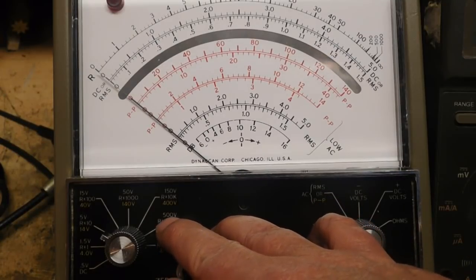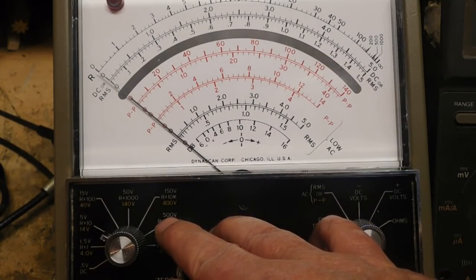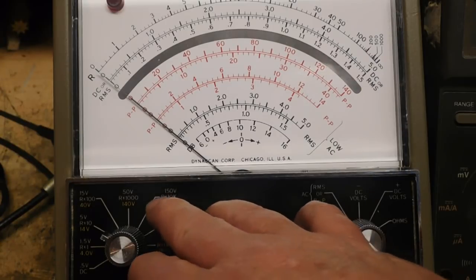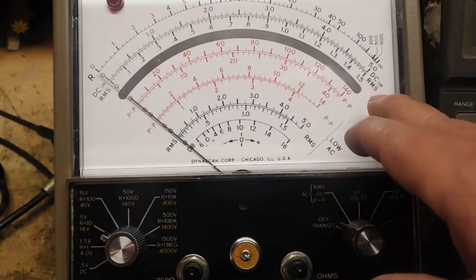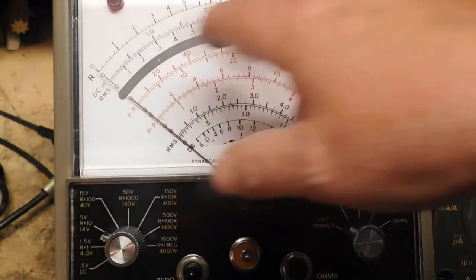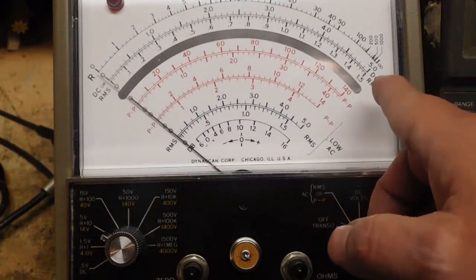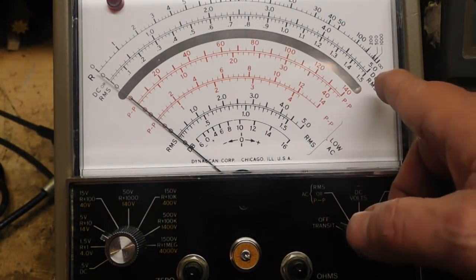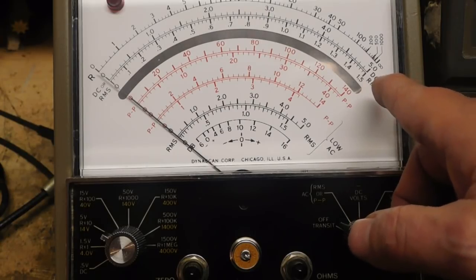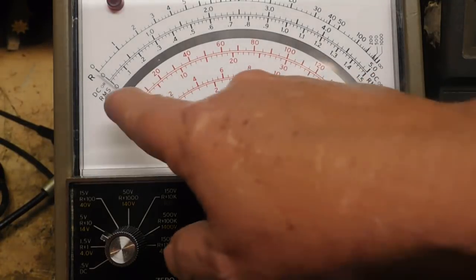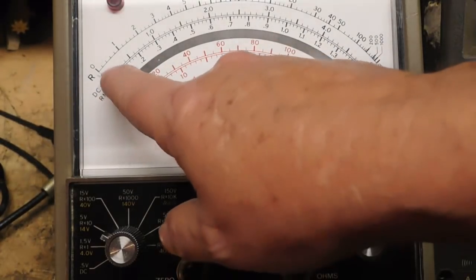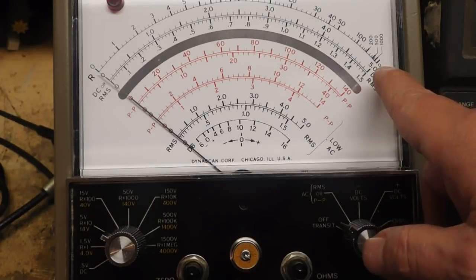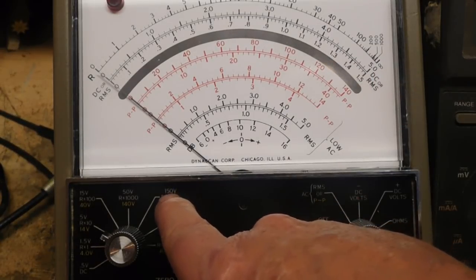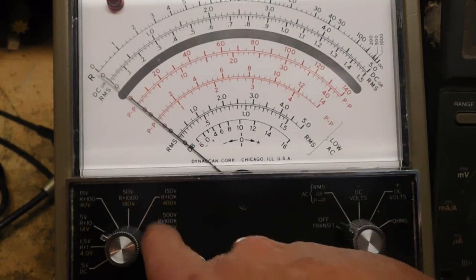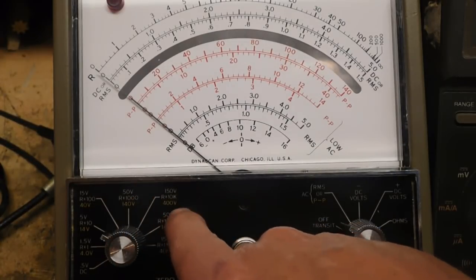Your scale is full scale on these voltages, so whatever range you set it to is full scale. You pick out the scale from what it says on the meter. Pretty much all DC and RMS voltages are measured on these two scales here, either the 0 to 1.5 or the 0 to 5, and you multiply them times whatever factor the range is set on.